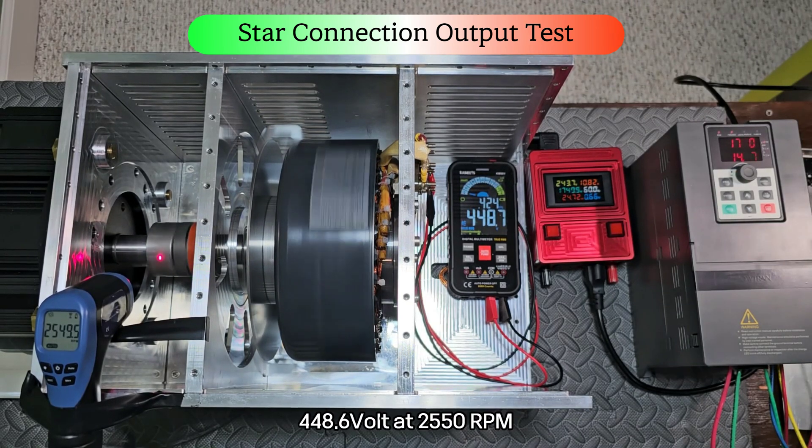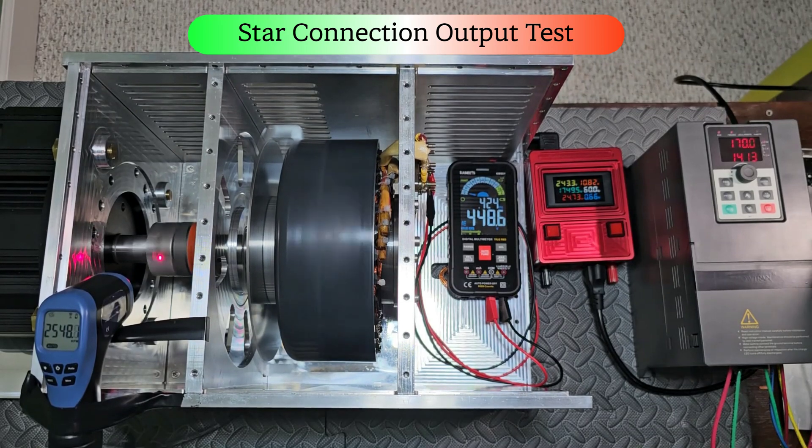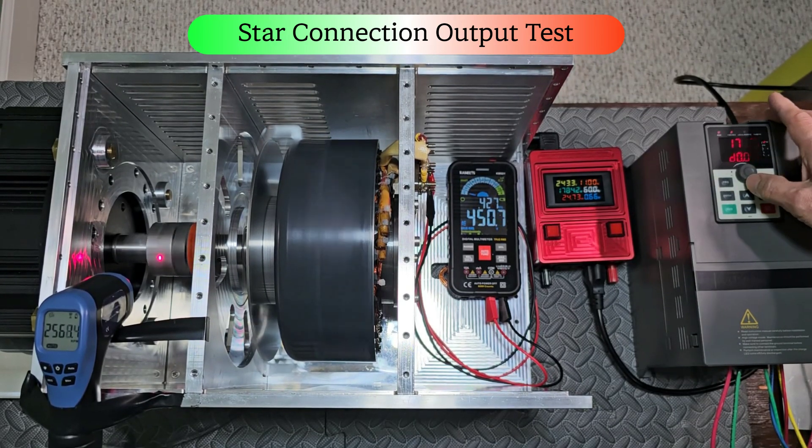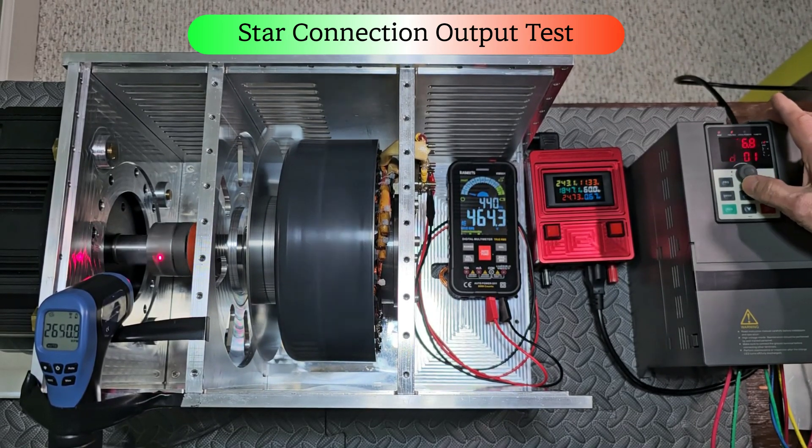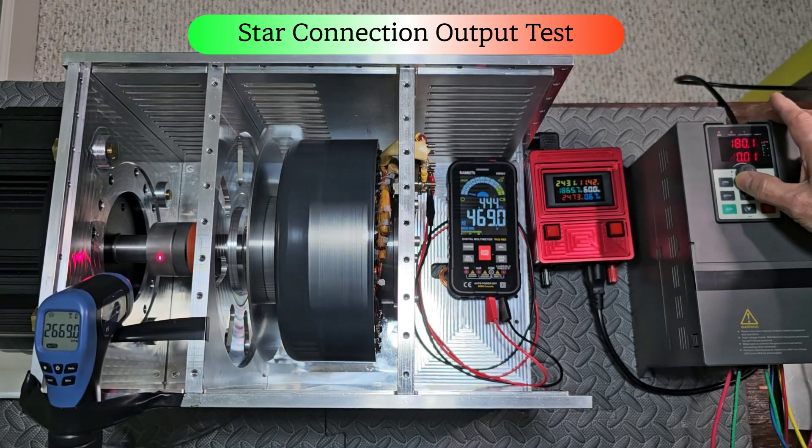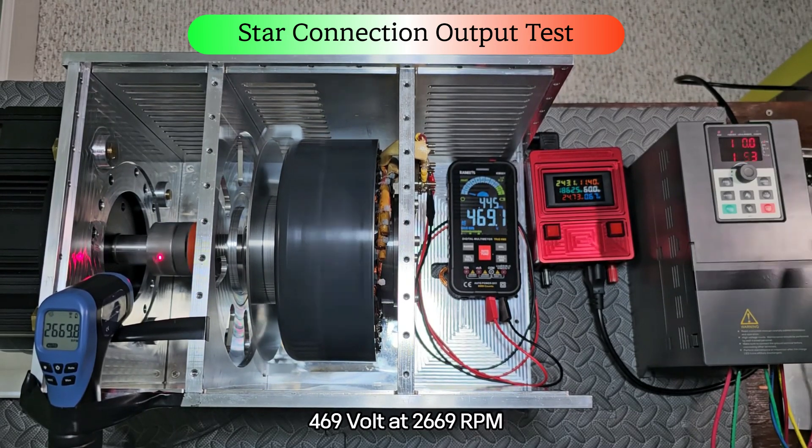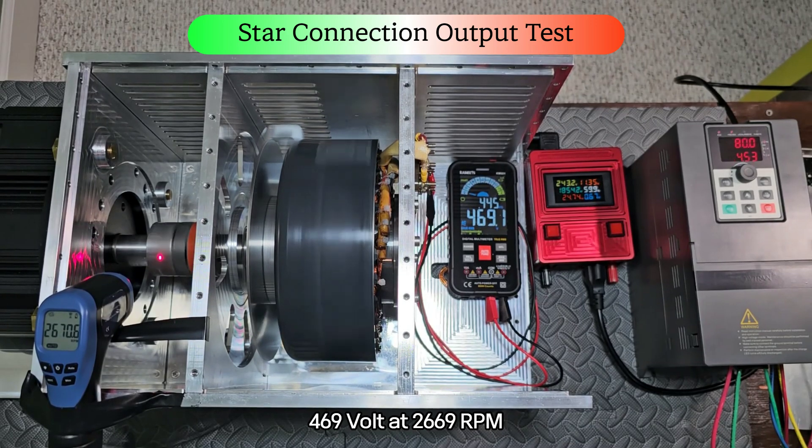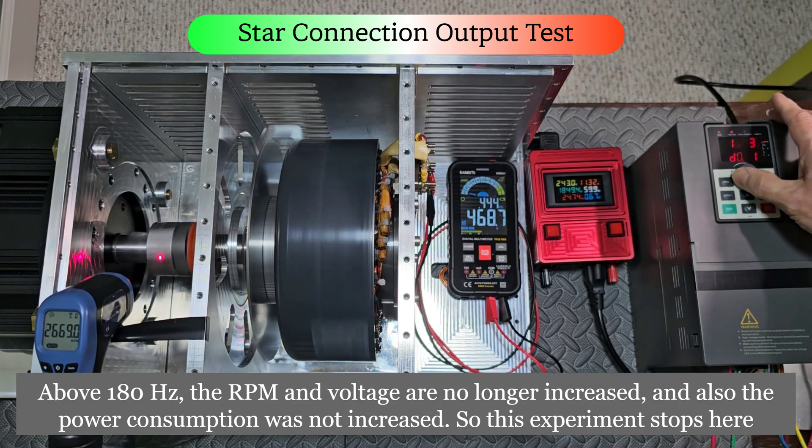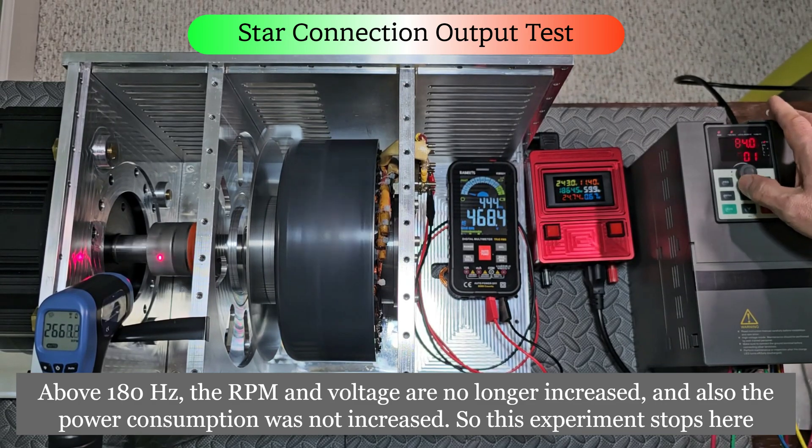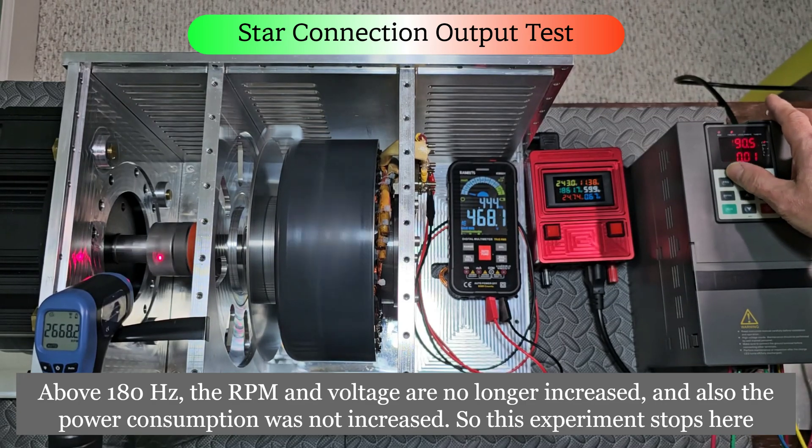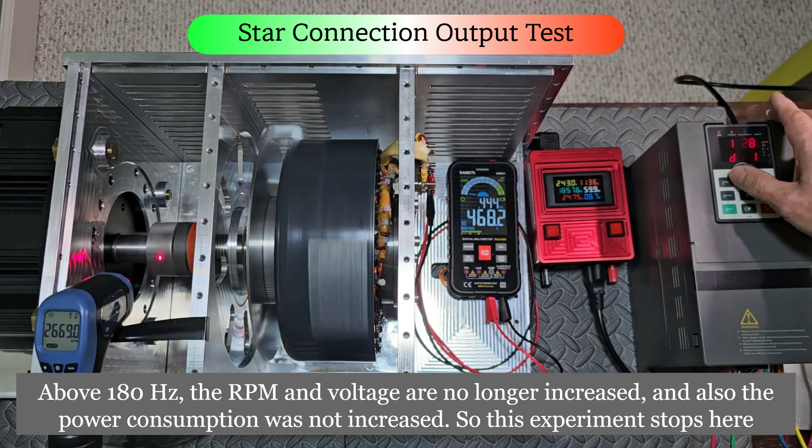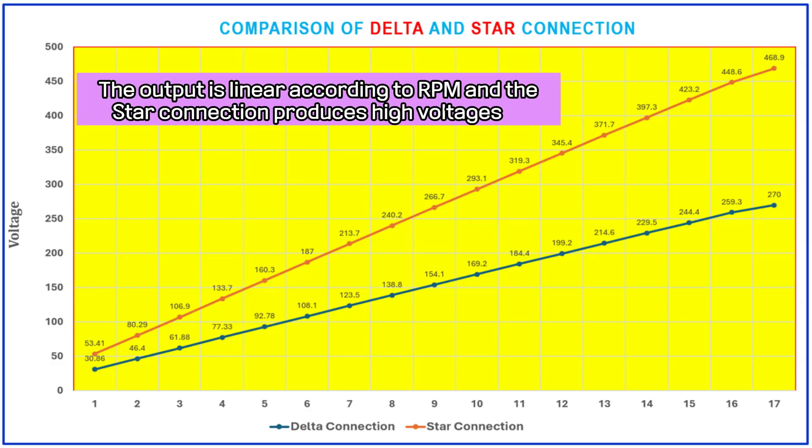The output is 423.2 volts at 2400 RPM, 160 hertz. System uses 1494 watts now. 448.6 volts at 2550 RPM. 469 volts at 2669 RPM. And also the power consumption was not increased. So this experiment stops here. The output is linear according to RPM, and the star connection produces high voltages.